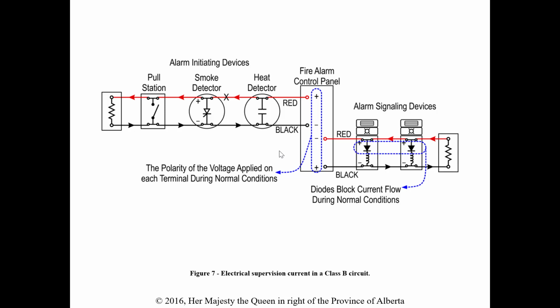So that's the first thing we'll talk about, conventional systems. And we're going to hook them up as Class B or Class A. In a conventional system, we have our control panel, our initiating devices, and our signaling devices. The big difference between a Class B and a Class A is that on a Class B, we go through an end-of-line resistor. You can see that here in the initiating circuit and in the signaling circuit. So we have current flow through all these devices, through the end-of-line resistor and back to the panel.